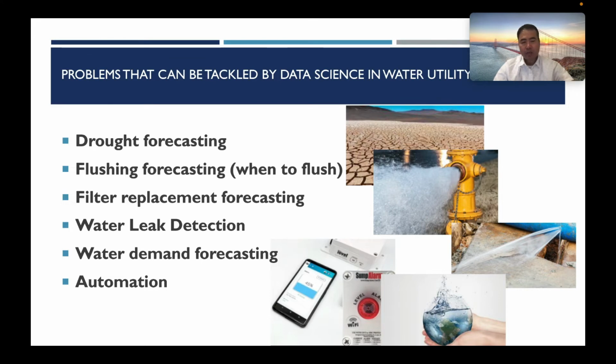Another part that I'm working on is filter lifespan forecasting. We forecast the differential pressure of the filter, and when this is way too big, then it's time to replace the filter. We have a lot of data in our data warehouse, in many different areas, and I'm using that data to build the models.